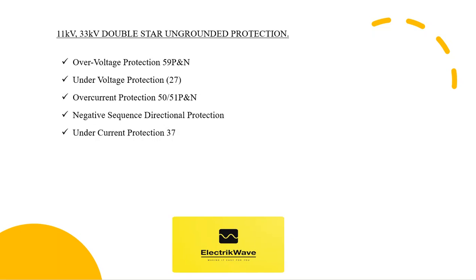11kV, 33kV double star ungrounded protection can be equipped with over voltage protection 59P and N, under voltage protection, over current protection, negative sequence directional protection, and under current protection. Now we will see the above protection requirements in detail.